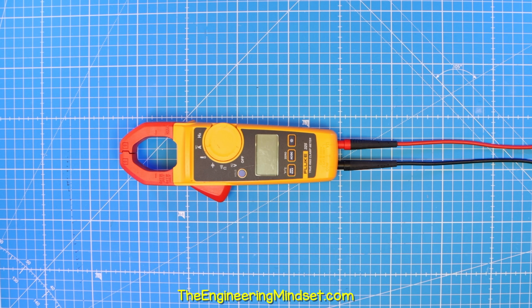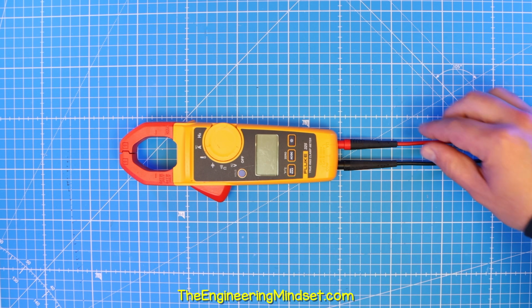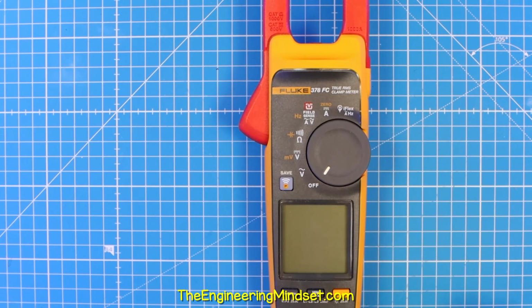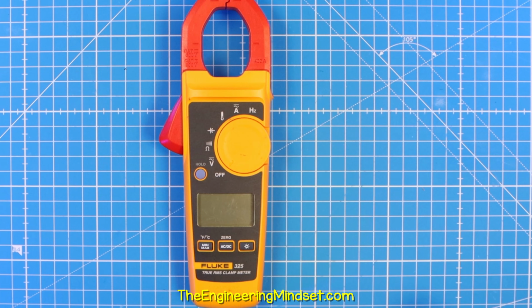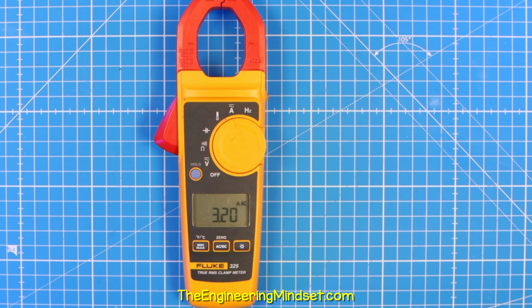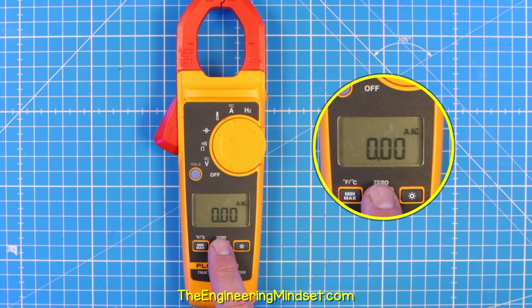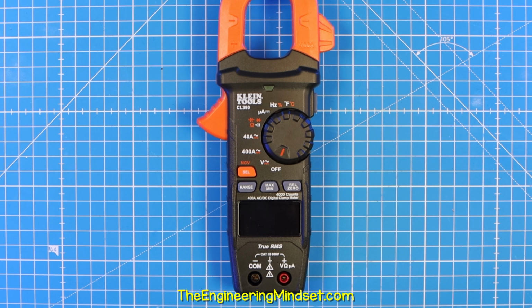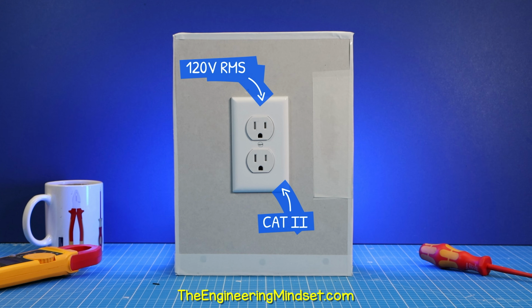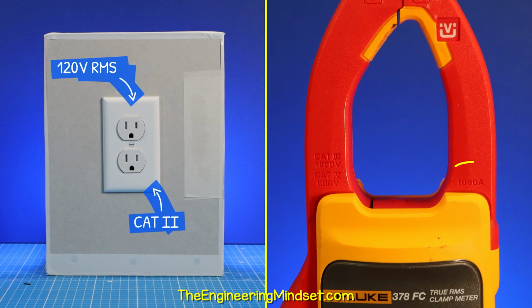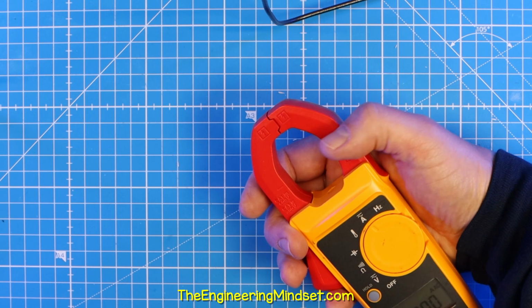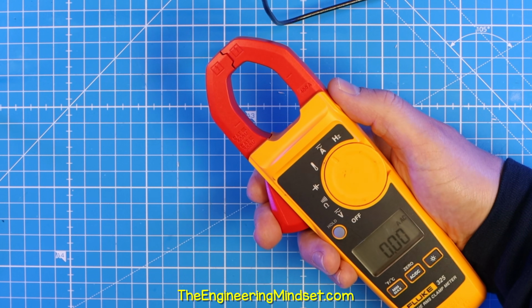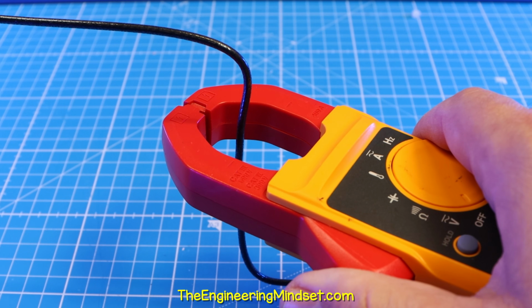To measure the current, we will use the clamp and not the leads, so ensure that these are removed. Then find and select the AC current function on your auto range meter. Some combine both functions into one symbol. You might need to press the button to switch between AC and DC. The screen will show 0 after a few seconds. I will explain manual range in just a moment. You need to assess the circuit and ensure that the current and voltage won't exceed the limits of your device. Keep your hand behind the barrier, squeeze the trigger to open the jaw, and then clamp around the wire.